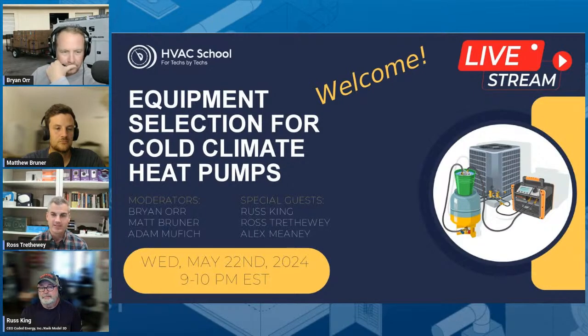So it adds to the cost and adds complexity, of course, but we're just not in a great climate for dealing with this. I wish we lived in Phoenix, from a climate perspective, but we don't, and so yeah, we definitely have some extra challenges there. And the tricky part with these is that when you're sizing for heating, of course, you're oversized for cooling, to your point, Brian. When you're dealing with these latent loads, we have a high performance heat pump. It's oversized for our cooling loads.